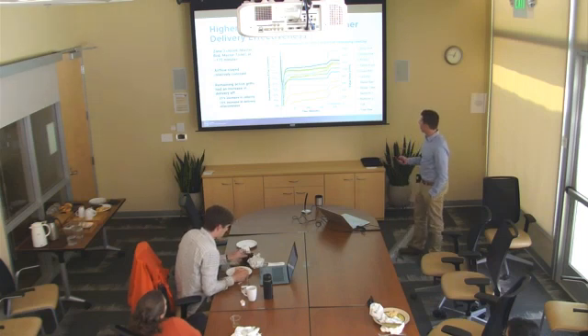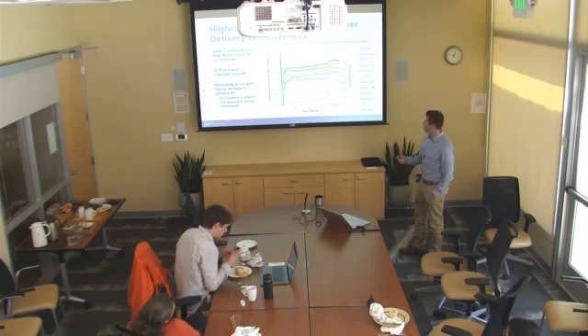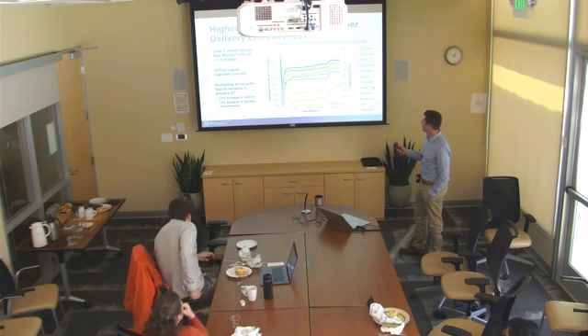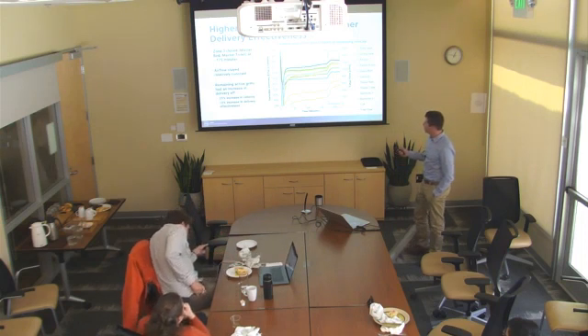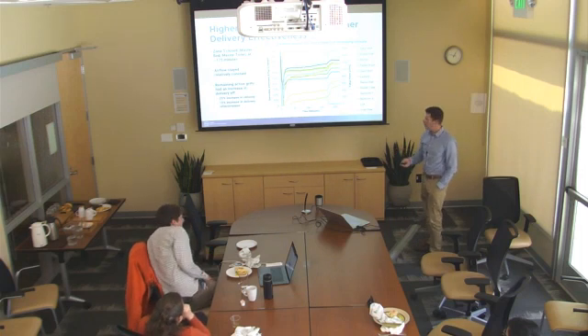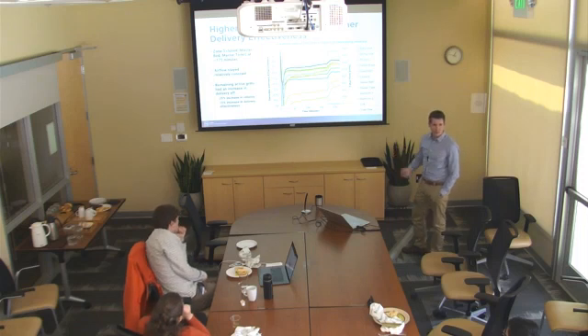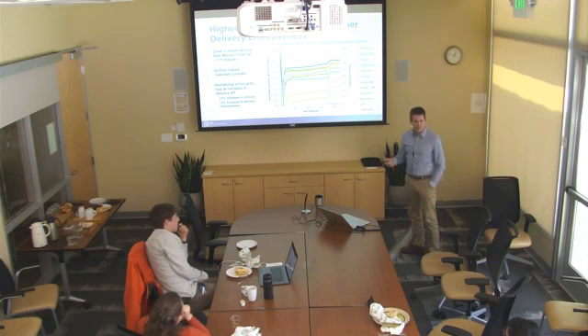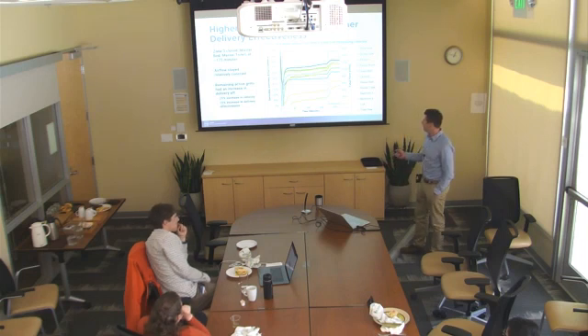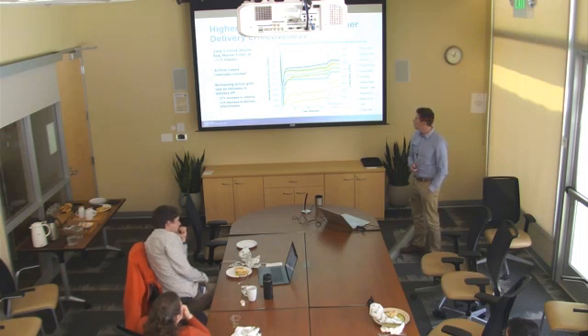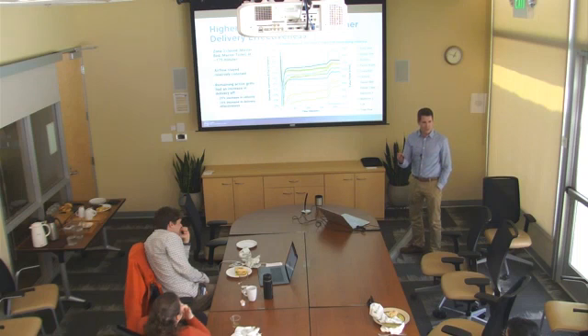At 175 minutes, one of the zones shut down. This green line shows the airflow of the unit. When that zone shut off, so the master bedroom and another bedroom shut off, you'll see there was a slight dip in the airflow, but essentially the airflow remained constant throughout this process. So that meant the airflow in these remaining ducts immediately went up. They went up by about 25% in velocity, and there was an immediate, on average, 10% increase in system COP. So this is kind of a real-time demonstration of the impact of duct velocity.